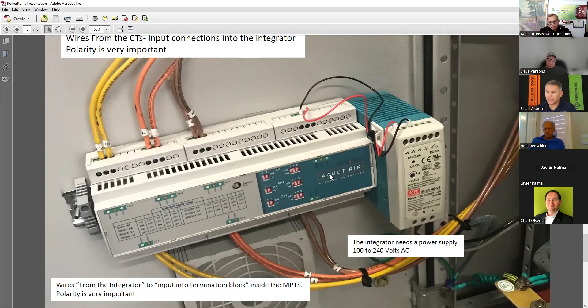There's one more mistake that happens. Do you see the shield has not been connected, right? There's a third lug here. Have you noticed? In this particular job, the shield is ignored. The ground is ignored. So what happens is when you ignore this, sometimes the positive and negative are here in the second and the third, so you're not even in the right place. There are 3 lugs. That's another mistake that happens, and you keep hunting for hours together to find it.